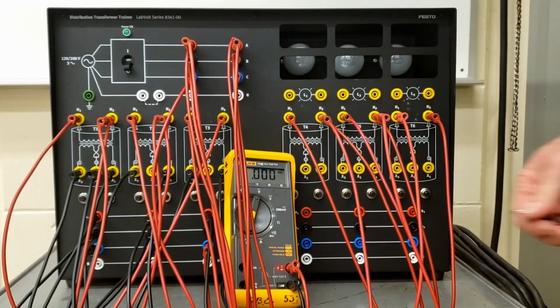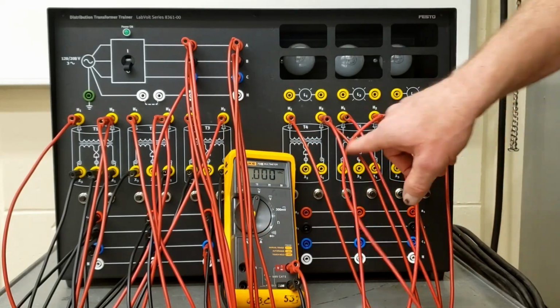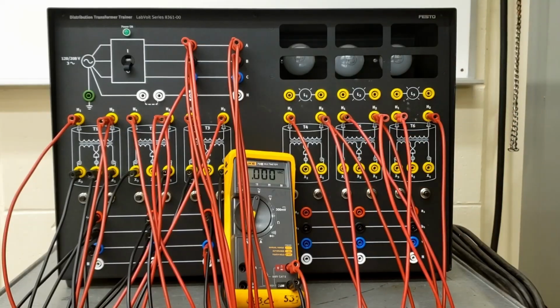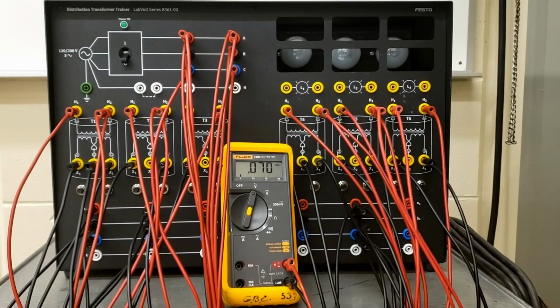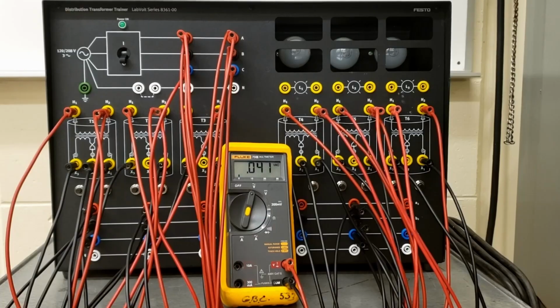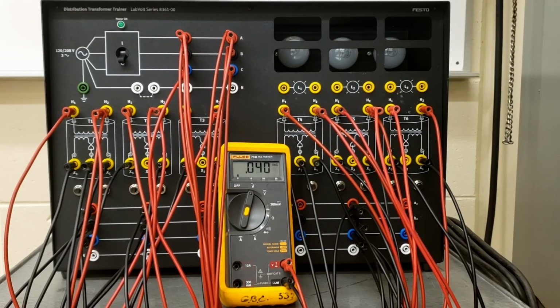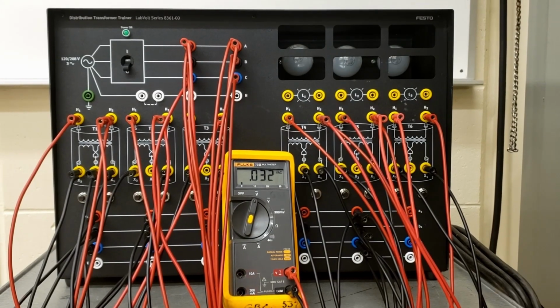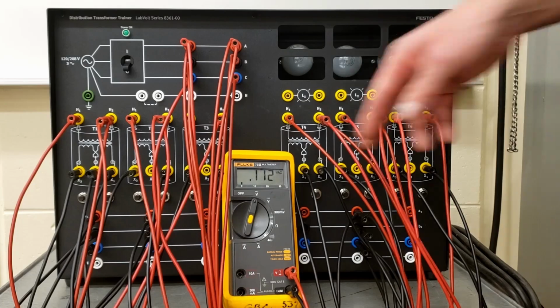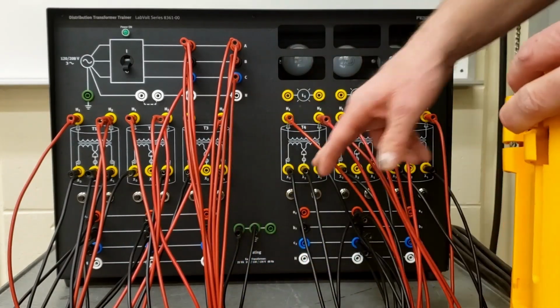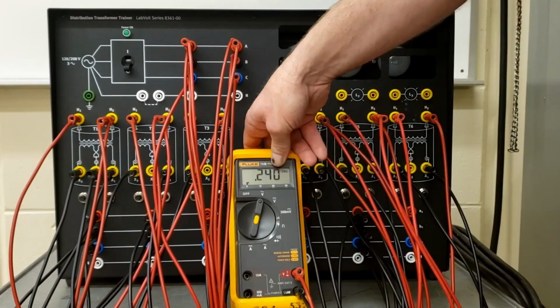Let me pause here and reconnect with the 180 degree phase shift on the secondary side. On page 9, you can see the 180 degree phase shift diagram, that's figure 1-7. You'll see X3 goes to A and X1 goes to B, so it's 180 degrees phase shift from the previous diagram. You'll also notice the X2s are tied to ground there.